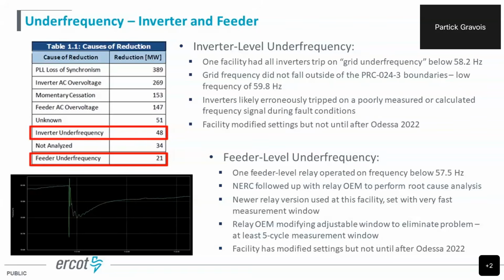We also had a feeder breaker trip due to under frequency, and this was low 57.5. So this is something we've really been trying to work on in the industry as a whole. On the bottom left, we've got PMU data from out west. So you see the fault occurs, we have this sharp decline in frequency during the fault conditions, then it returns, and then it starts to drop due to the loss of generation on the system. So frequency ride through is really meant for the grid frequency due to this loss of generation. It really shouldn't be tripping off during these fault conditions, because you're trying to read a frequency in a matter of 100 to 200 milliseconds.